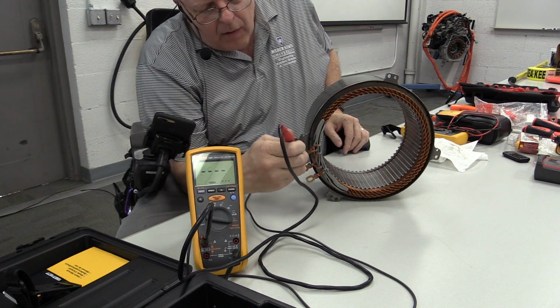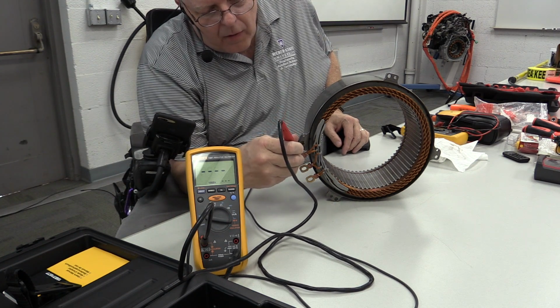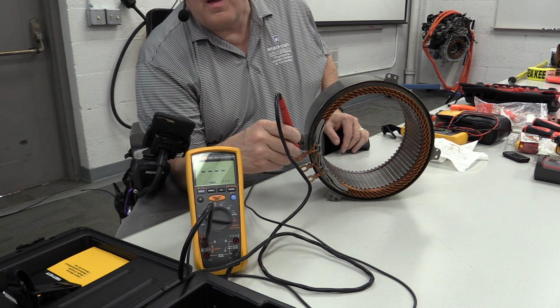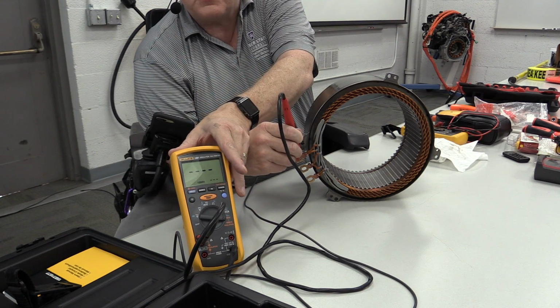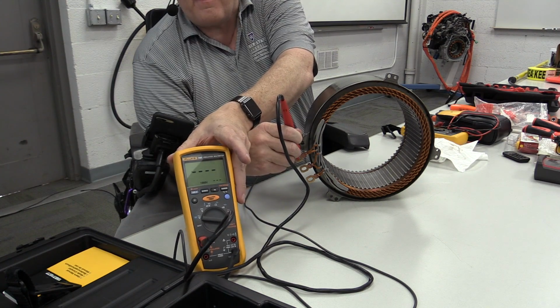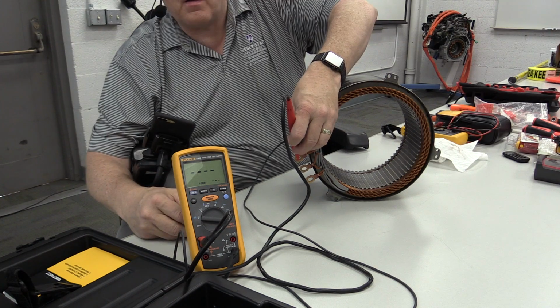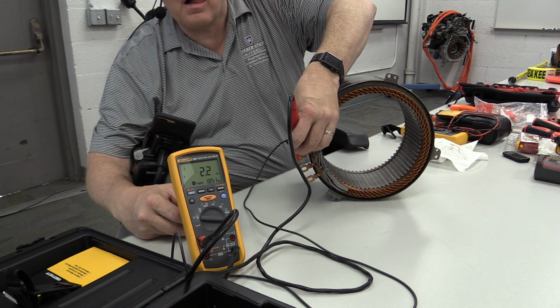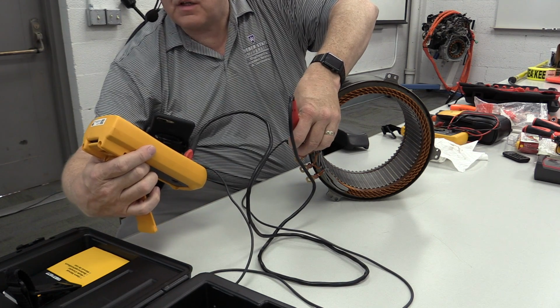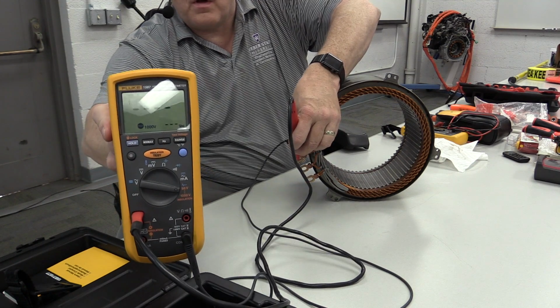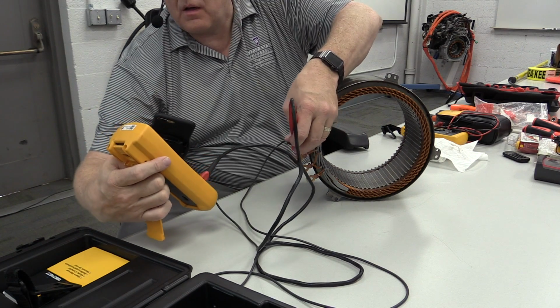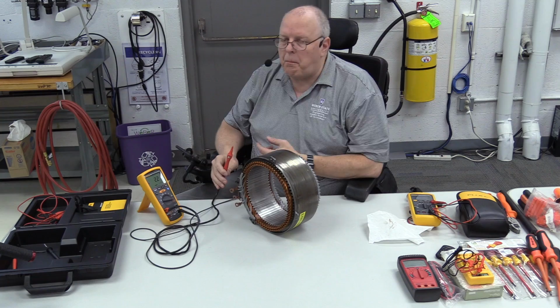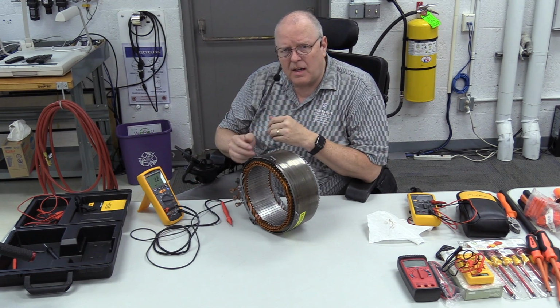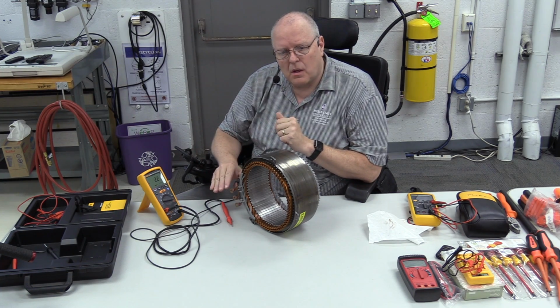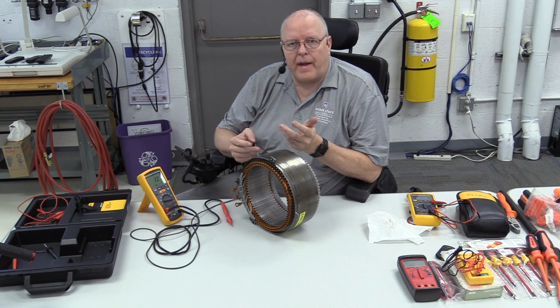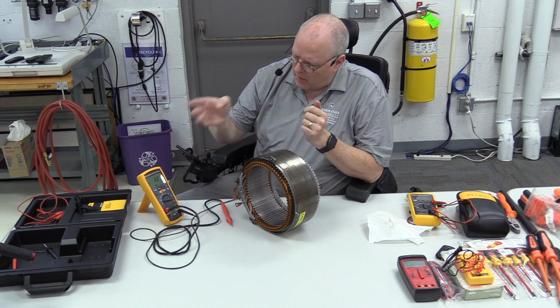So I'm going to put that right here on the copper conductor. Just kind of lay it here sideways, and let me get the meter positioned where we can read it. Okay, here we go. So it's telling us it has 2.2 gigaohms with 1000 volts applied. 2.2 gigaohms. 2.2 billion ohms of resistance between these two. And each vehicle manufacturer will have a minimum amount of resistance allowed. And if it's higher than that, then we're okay. So whatever that may be.